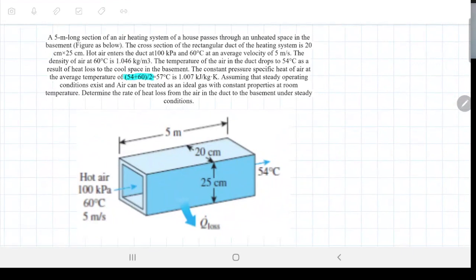That's the first mistake of this engineer, because we have an air system, an air duct going through the rooms and living room. At some point it has to go through the basement, but the basement is colder than the rest of the house. The cross section of the rectangular duct is 20 by 25 centimeters. Hot air enters the duct at 100 kilopascals and 60 degrees Celsius at an average velocity of 5 meters per second. The density of air at 60 is 1.046, and the temperature of the air after it passes through the heat loss in the basement is 54 Celsius.